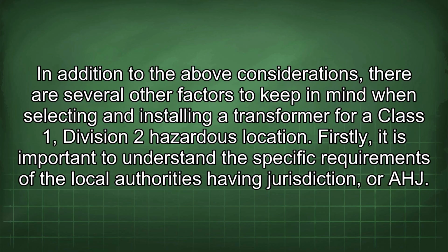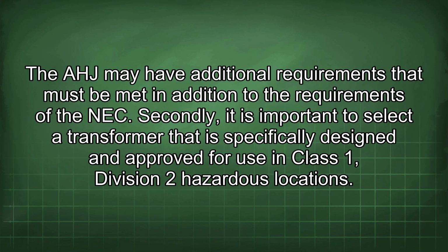In addition to the above considerations, there are several other factors to keep in mind when selecting and installing a transformer for a Class 1, Division 2 hazardous location. Firstly, it is important to understand the specific requirements of the local authorities having jurisdiction, or AHJ. The AHJ may have additional requirements that must be met in addition to the requirements of the NEC.